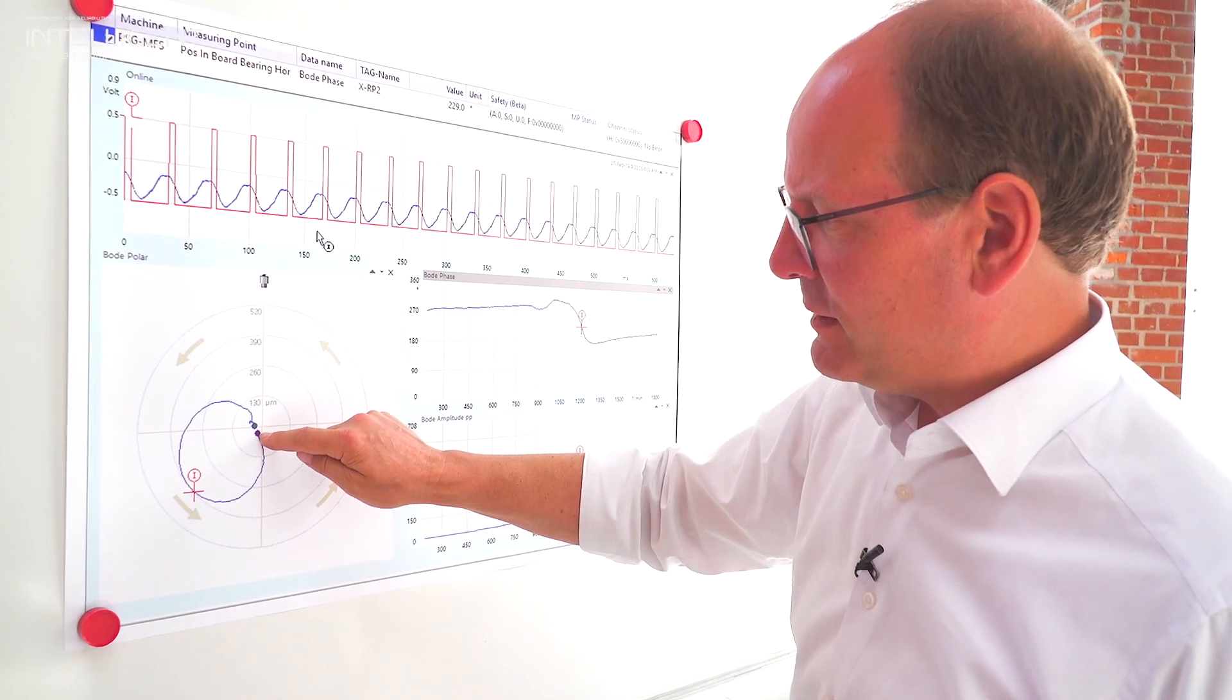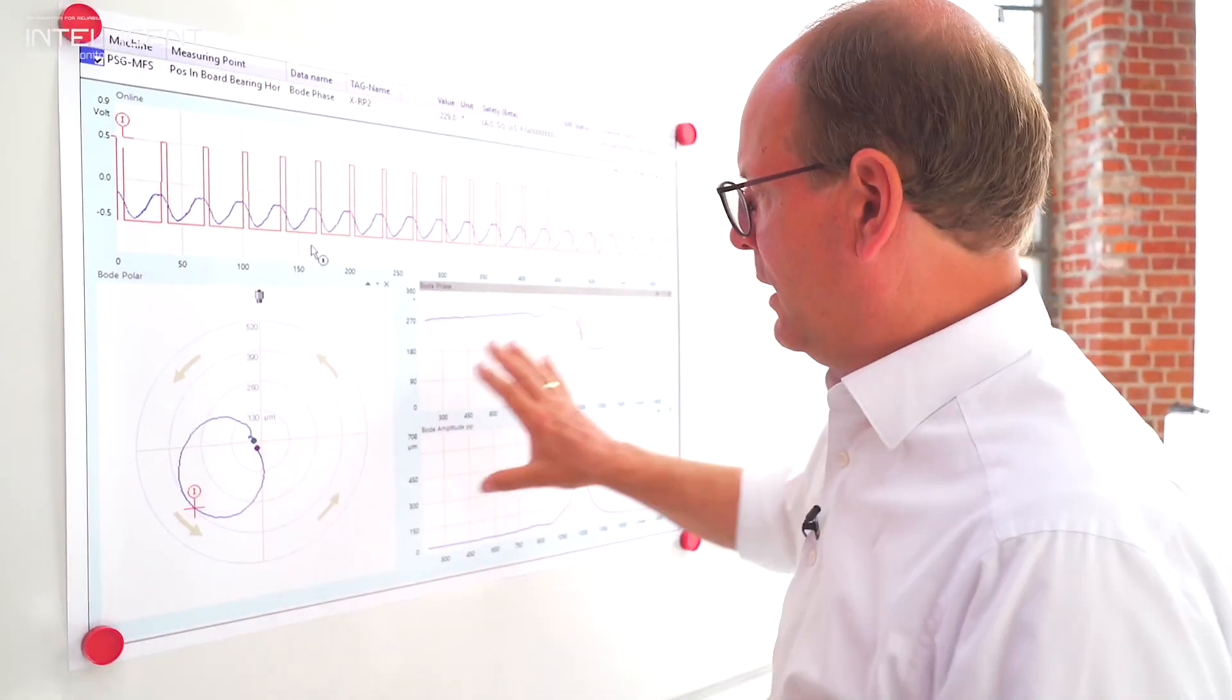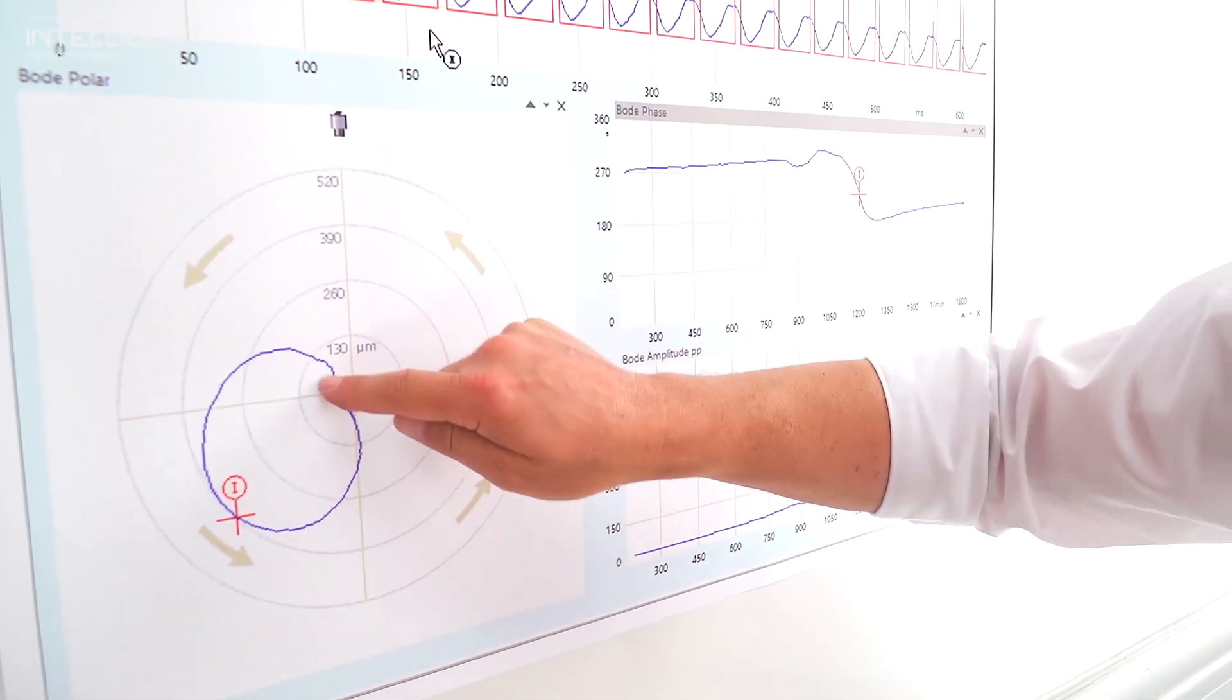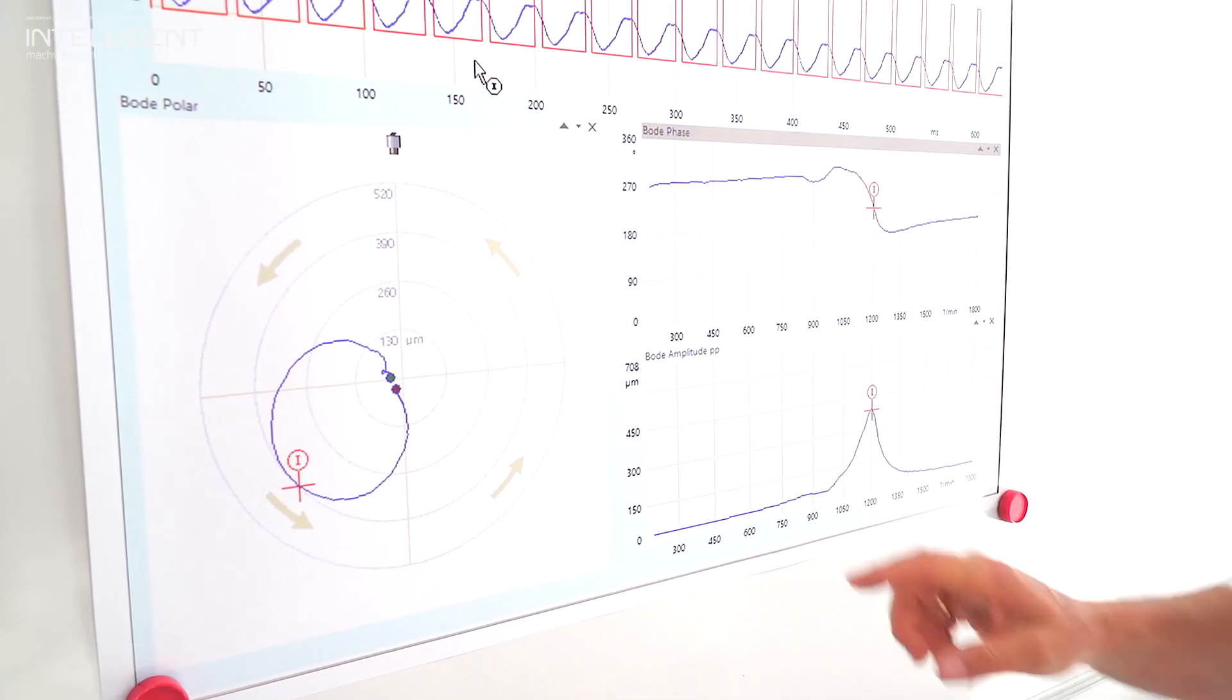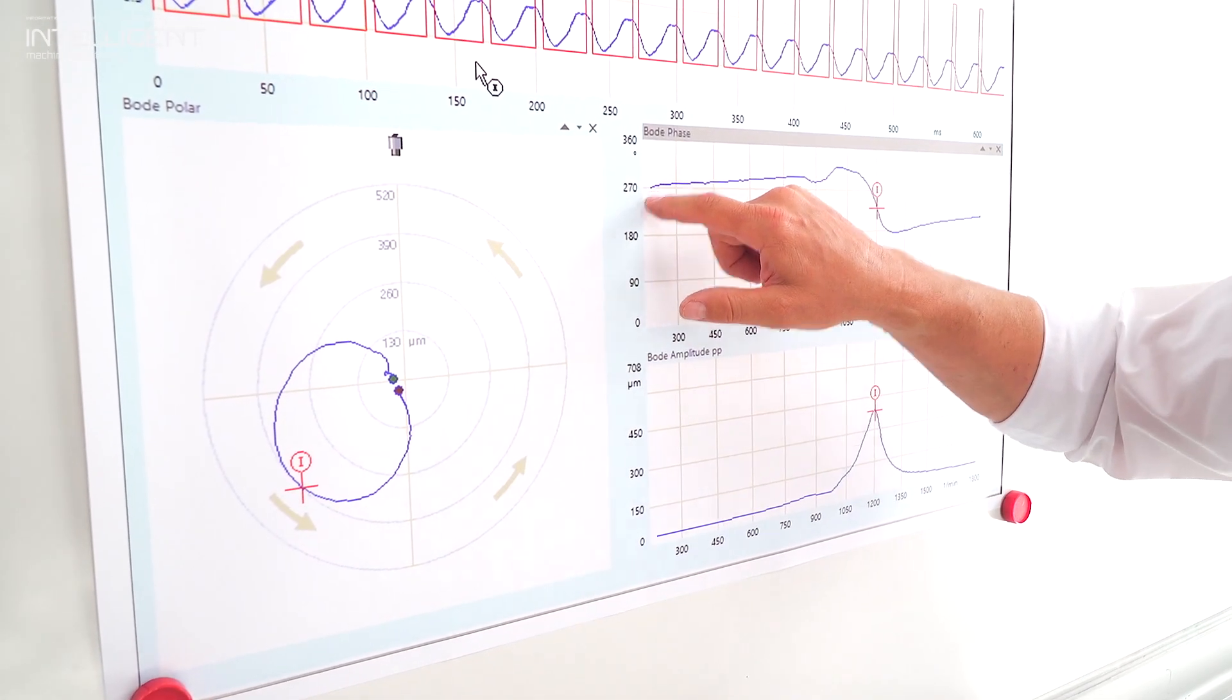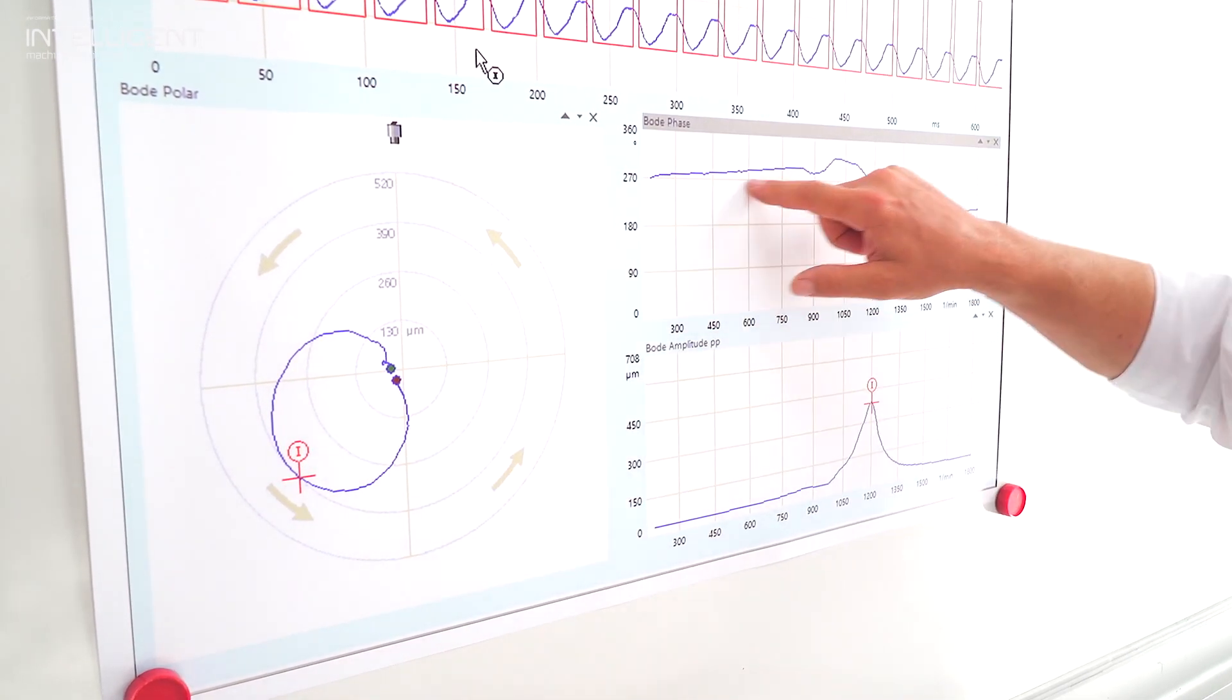This is the starting point when the machine starts. By using these two information we create the vectors. We see here all the different vectors creating a Bode Polar orbit. We see here also we are below 270 degree, and then after starting up the machine we are going over 270 degree.